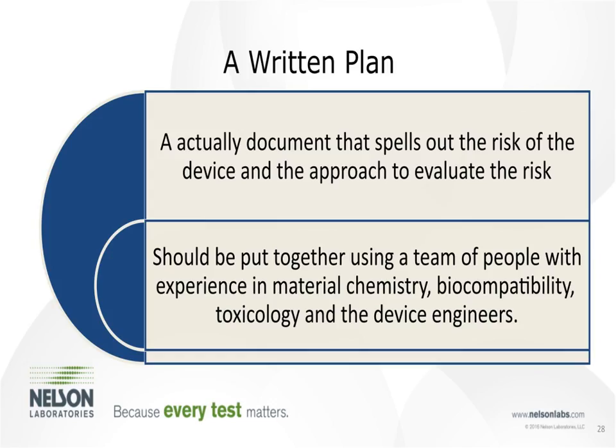I also want to make a point here that this plan is great if we submit it to the FDA, especially if you are trying to justify out of testing, because what you can do is a Q-sub or a pre-sub with the FDA, which is an official submission. I've also had companies that have really good relationships with reviewers that have done informal pass-throughs. But this is great because you get their feedback on the risk.